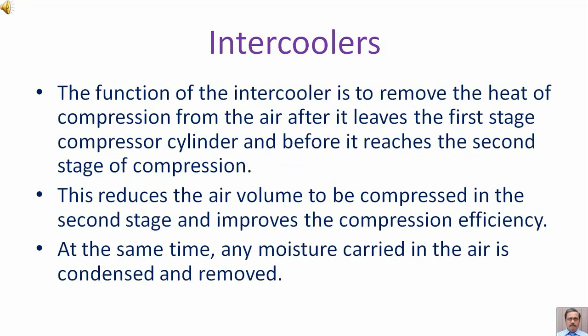The function of the intercooler is to remove the heat of compression from the air after it leaves the first stage compressor cylinder and before it reaches the second stage of compression. This reduces the air volume to be compressed in the second stage and improves the compression efficiency. At the same time, any moisture carried in the air is condensed and removed.